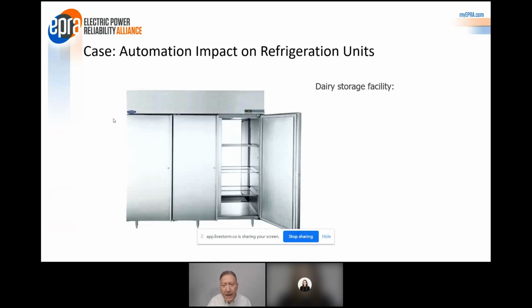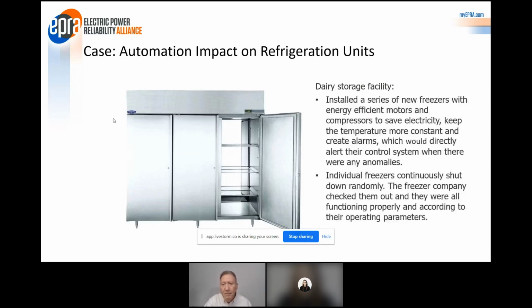They put in a $1,500 controller transformer. This was a million-dollar problem, solved for less than $2,000. It took the harmonics out, and they ran, and they still run to this day. It was a better solution. But think about it—if that legacy electrician hadn't known there were harmonics, they might have spent millions of dollars sending stuff back.